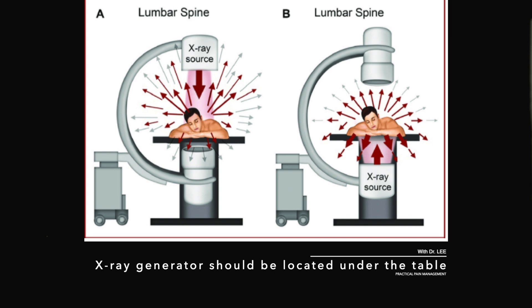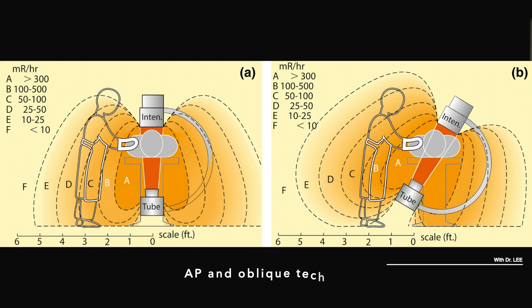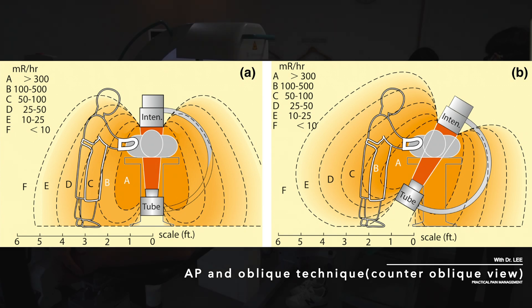First, to reduce radiation hazard to the operator, the X-ray generator should be at the bottom, under the table, not above the table. If the X-ray generator is located above the patient, scattered radiation intensifies to the operator. To reduce radiation hazard to the patient and operator, I try not to use lateral X-ray beam projection. I prefer to use AP and oblique technique. Sometimes I like to watch the object on counter-oblique view.